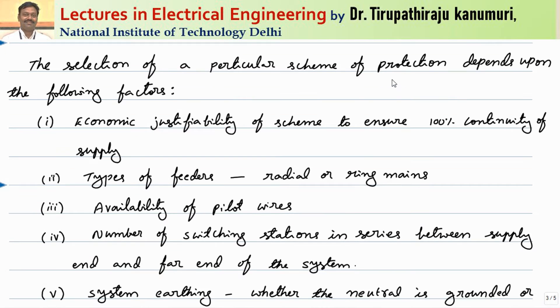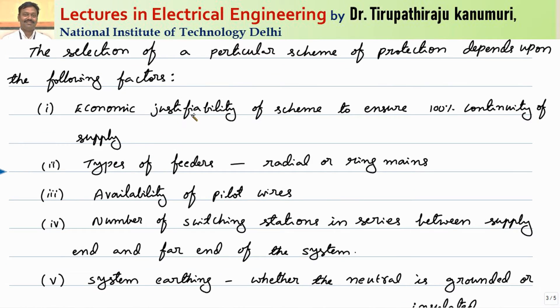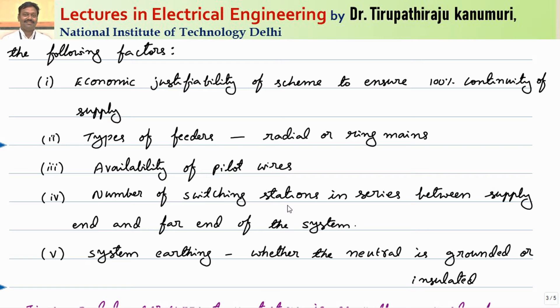The selection of a particular protection scheme mainly depends on the economic justifiability of the scheme to ensure continuity of supply. For low voltage systems, we cannot invest huge cost for circuit breakers, so we use HRC fuses, which can also provide sufficient overcurrent protection. Wherever proper investment is possible, we go for circuit breakers, which have advantages such as reusability. The next factor is whether the feeders are radial or ring main type, and the availability and cost of pilot wires.